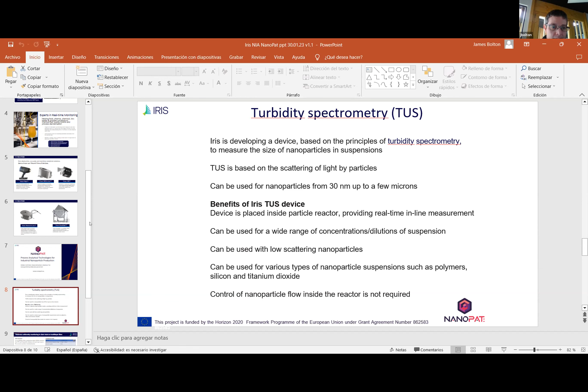The benefits of Iris's TUS device: the biggest benefit is it can be placed inside the particle reactor. So it provides real-time inline measurement of the particle size. It can be used for a wide range of concentrations or dilutions of the suspension. It also works with nanoparticles that don't scatter much light. The device is still able to collect enough signal. It can be used for nanoparticle suspensions such as polymers, silicon, and titanium dioxide. And finally, no control of the nanoparticle flow inside the reactor is required to use this device.